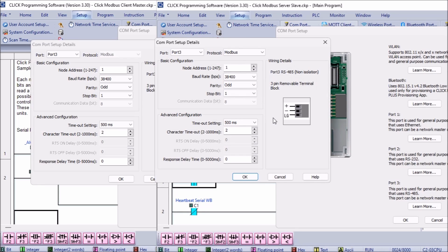Typically, the longer the physical cable runs, the slower you need to set the baud rate. Depending on your environment and the cable length, you may have to experiment with this rate.